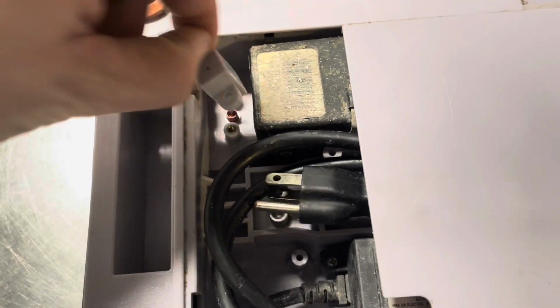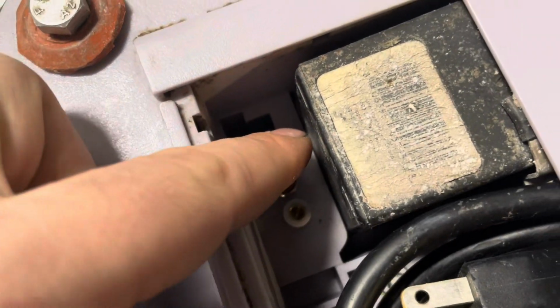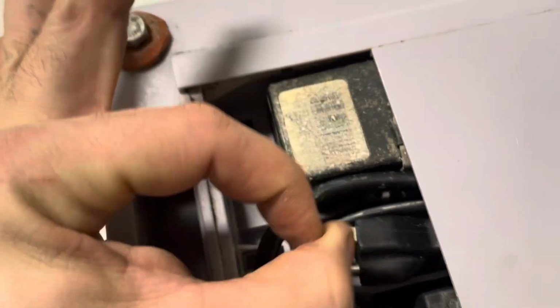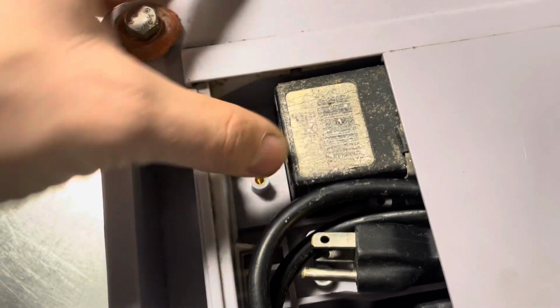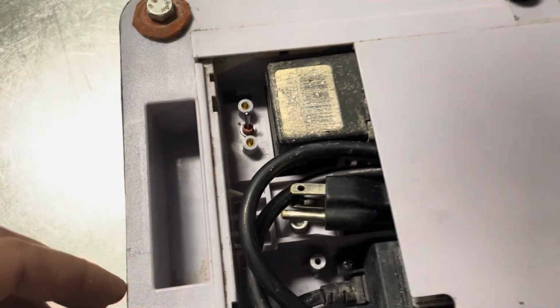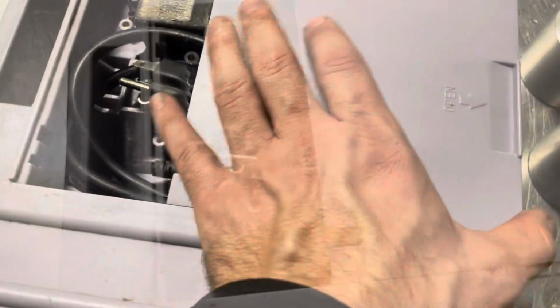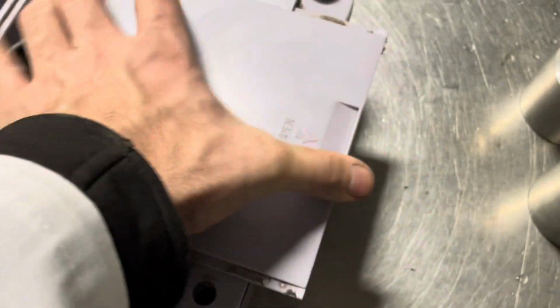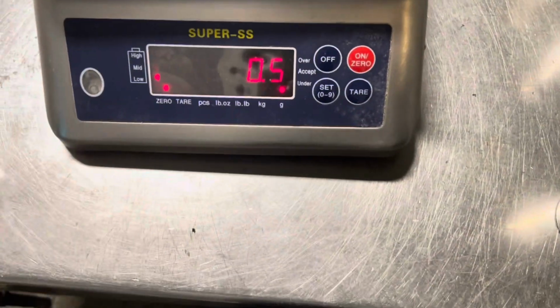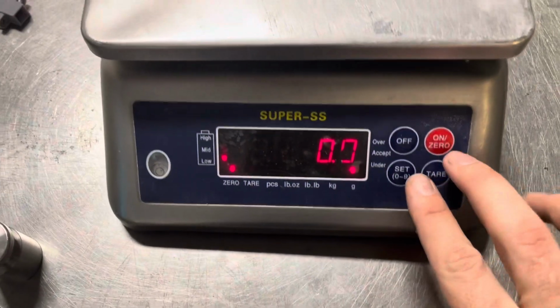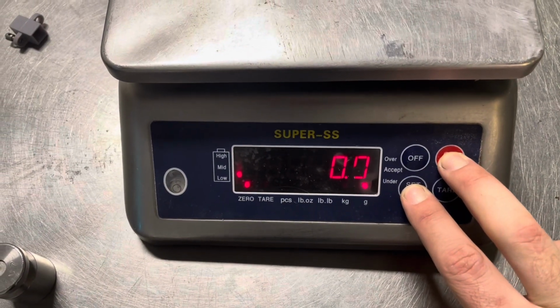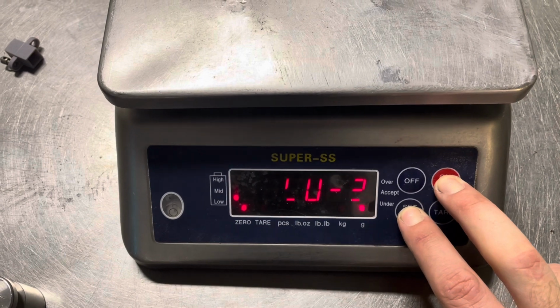Here we're removing the cover for the calibration switch to either lock or unlock the scale. Once it's unlocked, we'll switch over the scale, lock everything up, but you'll notice I don't have rubber feet. That's a problem, which I'll pull the scale and lock it into the table so it doesn't slide. Don't do that. You won't have an accurate calibration. But for the purpose of this video, that's how I'm doing it. I do not recommend it.